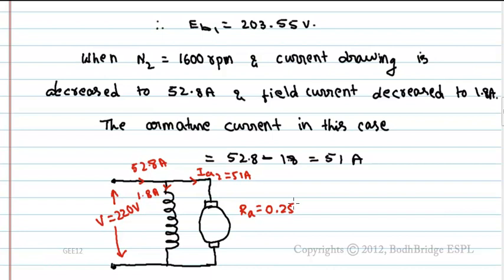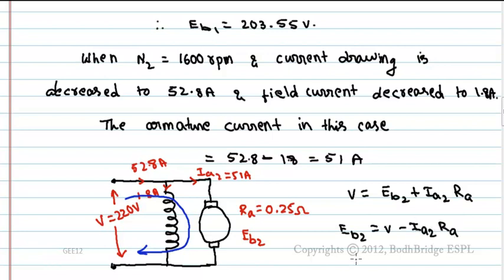So the armature current Ia2 equals 51A. Here Ra is 0.25 Ohm, Eb2. In the same way, by applying KVL to this loop, we get V equals Eb2 plus Ia2 into Ra. Eb2 equals V minus Ia2 into RA, which is 220V minus 51 into 0.25. This equals 207.25V.